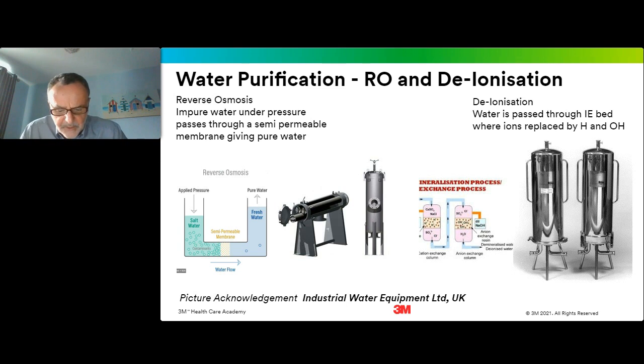Deionization is another method for purification. In this technique, a bed of ion exchange resins is used to swap cations and anions for hydrogen and hydroxyl ions, thereby reducing the salt level. So very pure water comes out of the other end of these processes. Again, some level of pretreatment is desirable, maybe to remove organic compounds, so an activated carbon filter would be used.